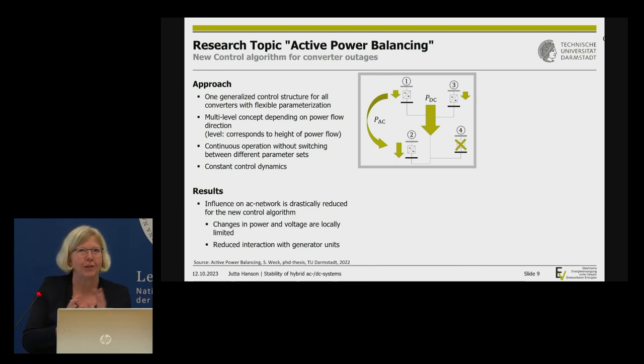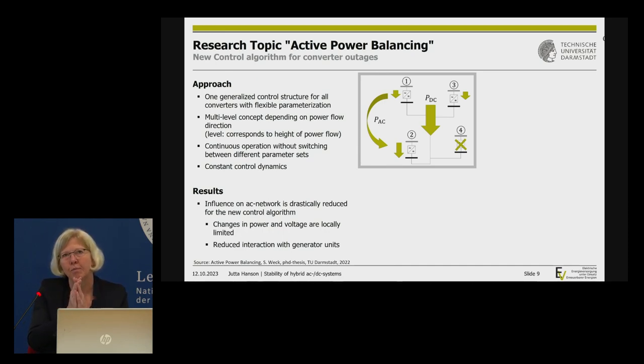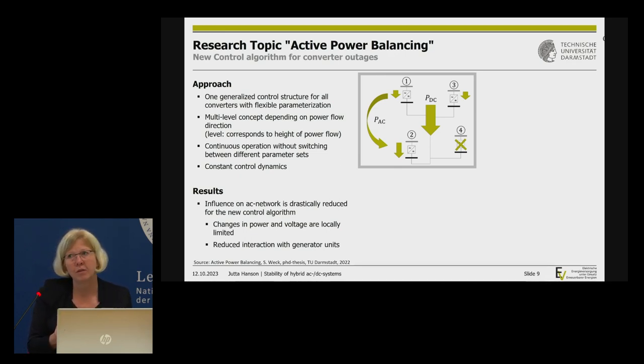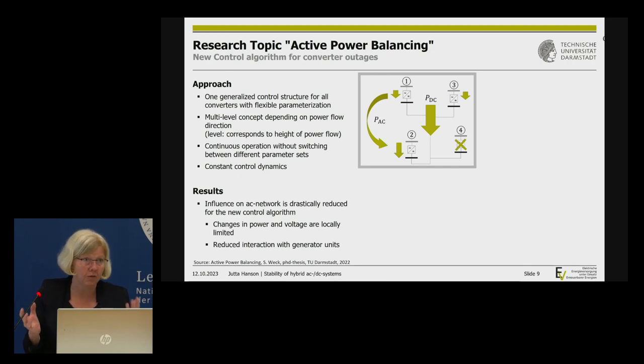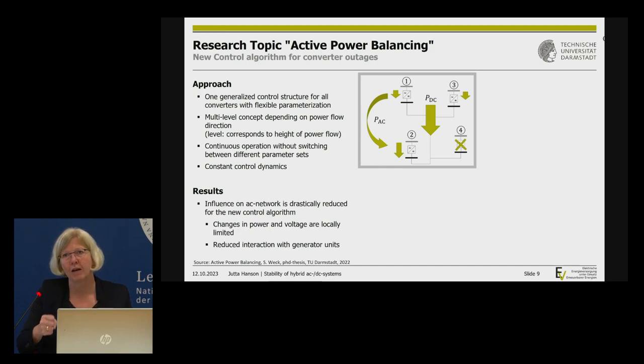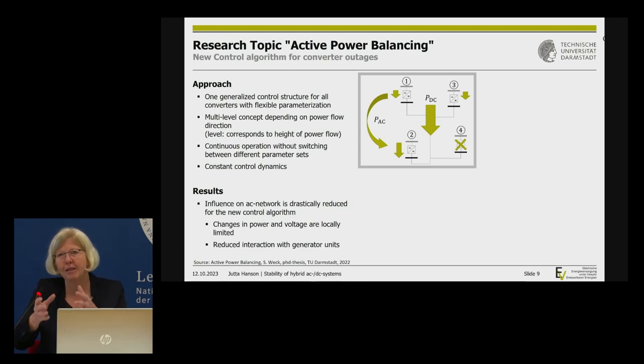Another example shows a network with power flowing north to south via both a DC transport link and the surrounding AC network. A key question is: what happens when one converter fails? Our control must manage residual power within the DC network. We found that pushing everything to the AC network causes very rough behavior — potentially cascading failure — so we should keep the fault more localized within the DC network.